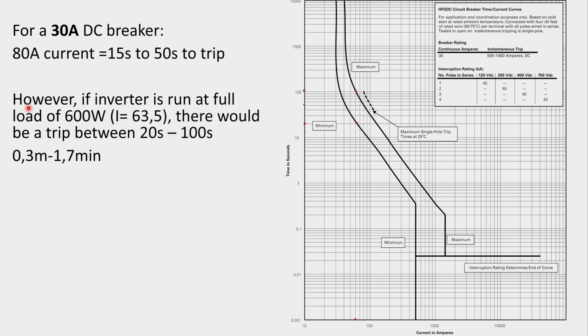However, now we have a problem, because if the inverter is run at full load of 600 watts, the circuit breaker will now trip between 20 seconds and 100 seconds. So that's 0.3 minutes to 1.7 minutes. And why that's a problem is if I connect maybe a laptop power supply or a device that overloads for a short time, or a device that has quite a bit of an inrush current, we might find that the inverter could handle it, but the circuit breaker now trips. And then we're getting something called nuisance tripping, because it's tripping when it shouldn't trip, because the inverter should be able to handle it. So this is the challenge when choosing the circuit breaker.